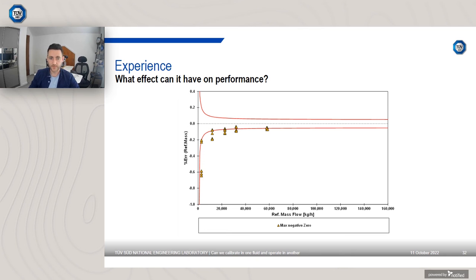So this is a calibration in liquid. If you were to use it for gas use, I think, in my opinion, some of the performance is basically muddied by the fact that the zero effects are potentially influencing the performance. Now, if you're going to try and put a curve fit through it, which I certainly wouldn't recommend, Coriolis meters shouldn't really be used with a curve fit because they're inherently linear devices at the upper range, then you're going to have significant deviations, and you could be correcting for the zero effects that might not be present when you install it and then check the zero in your installation. So I hope that you understand what I mean by that.